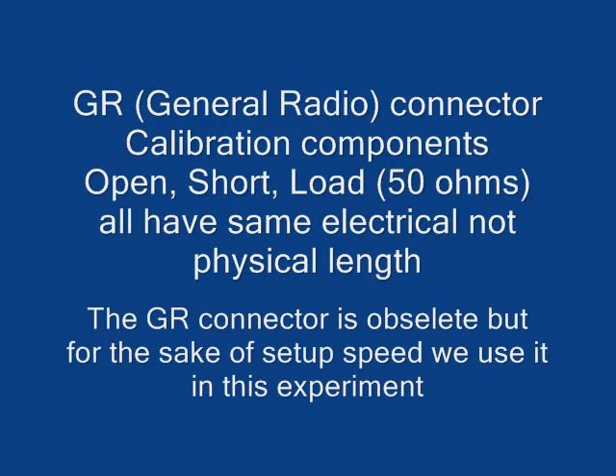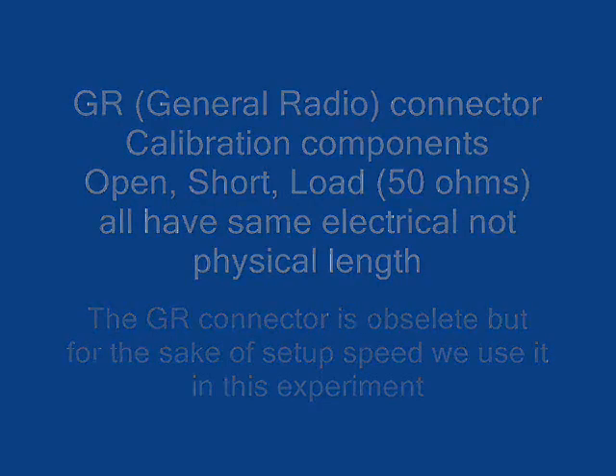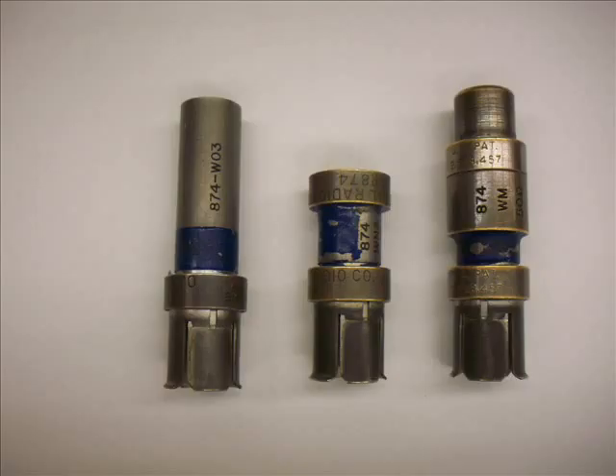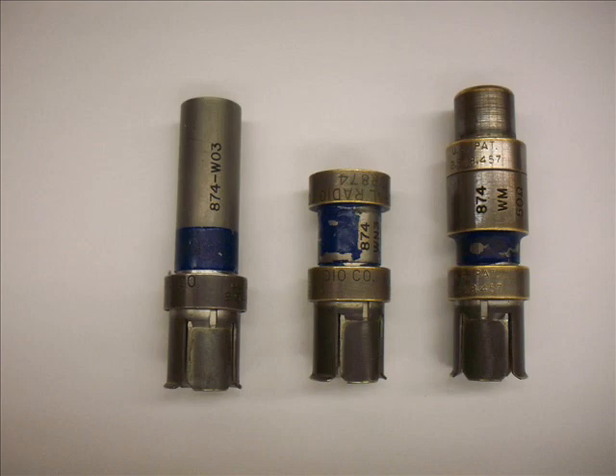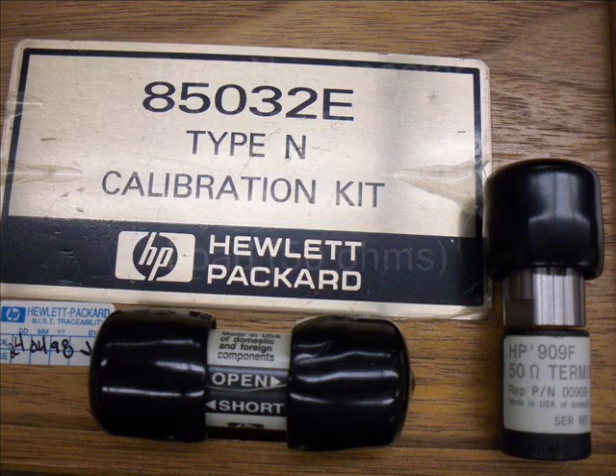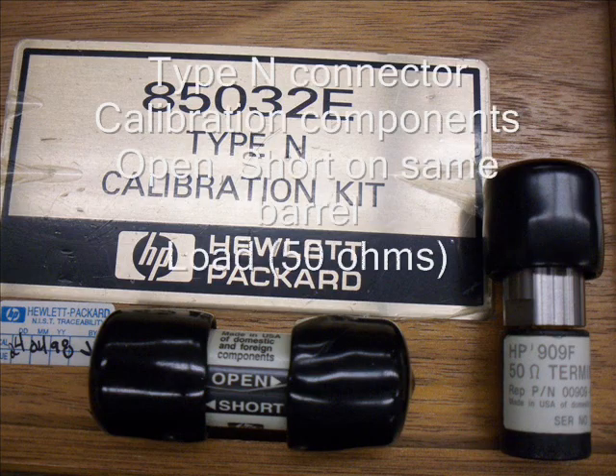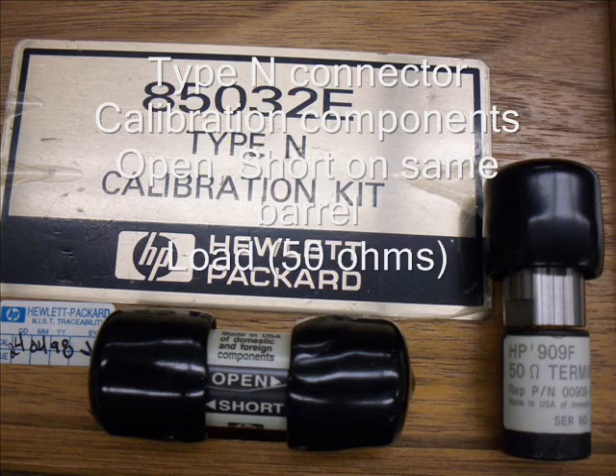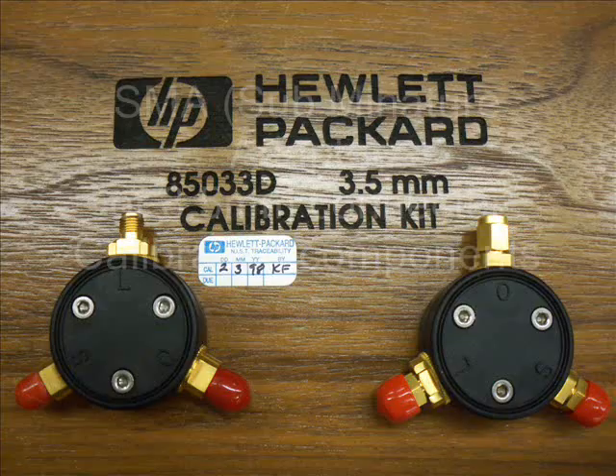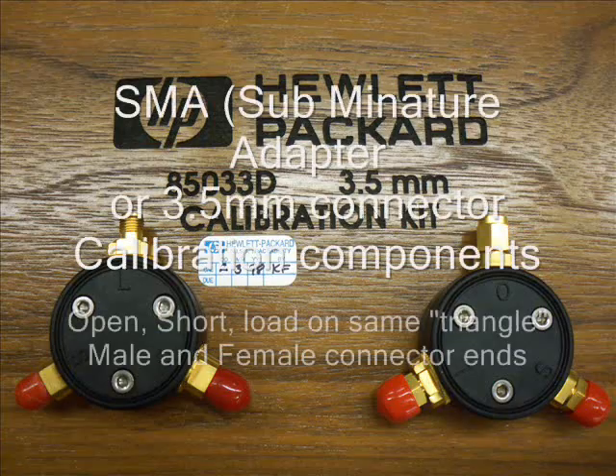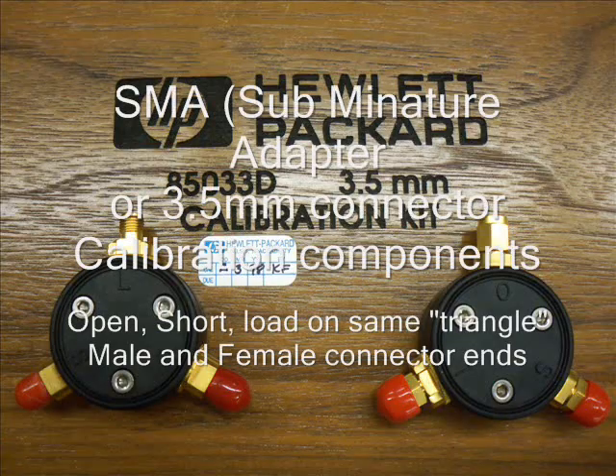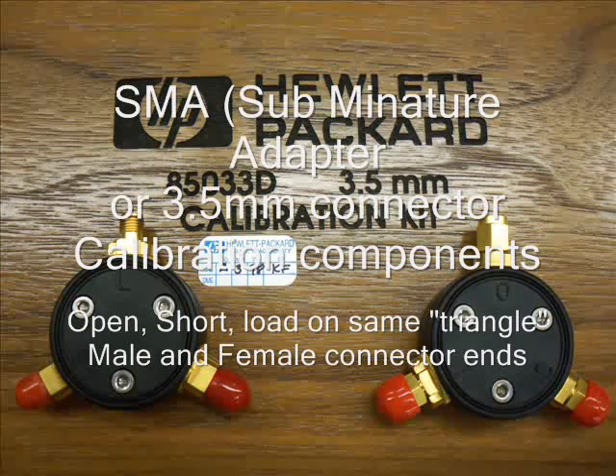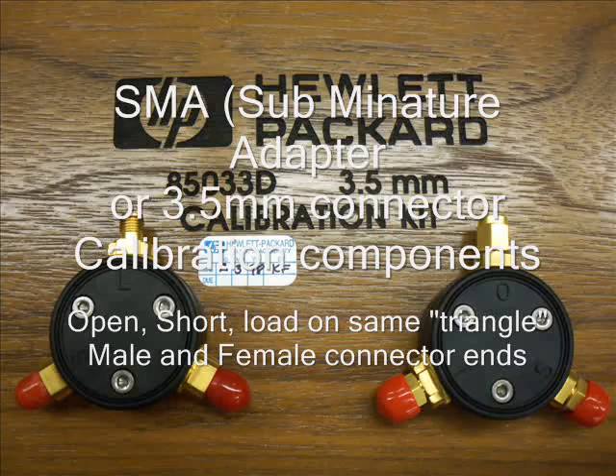Once the network analyzer has been calibrated with the appropriate connector set, whether it be GR, SMA, Type-N, or APC7 Precision 7, the end of the cable becomes the measurement phase reference for the network analyzer.